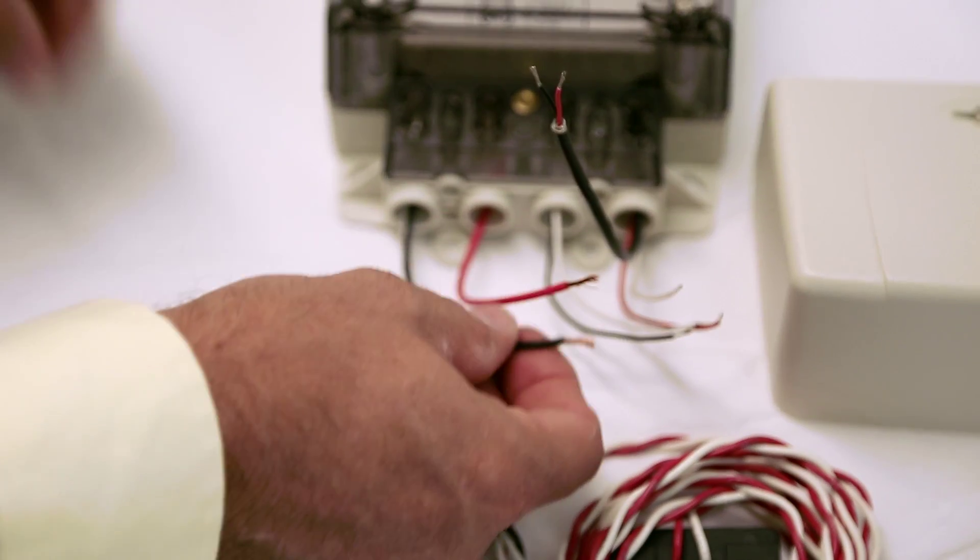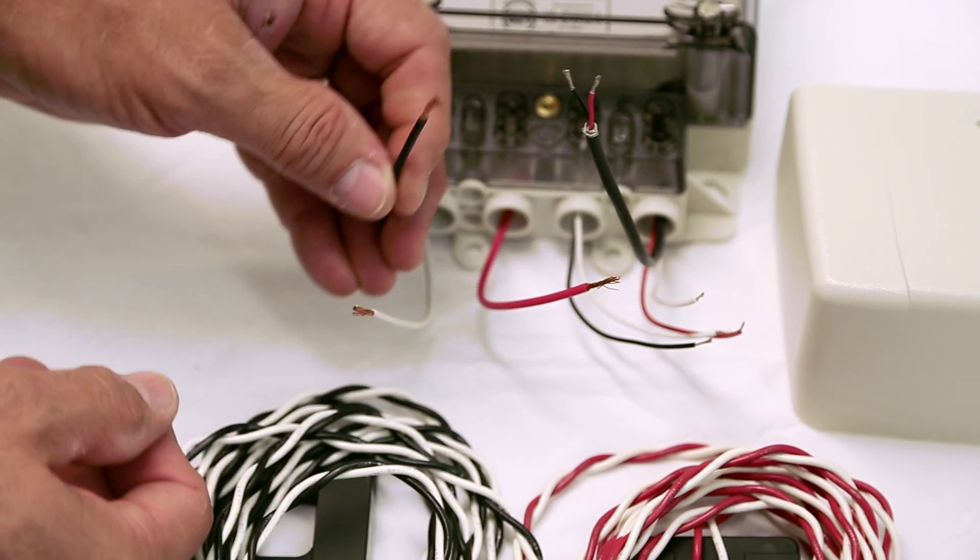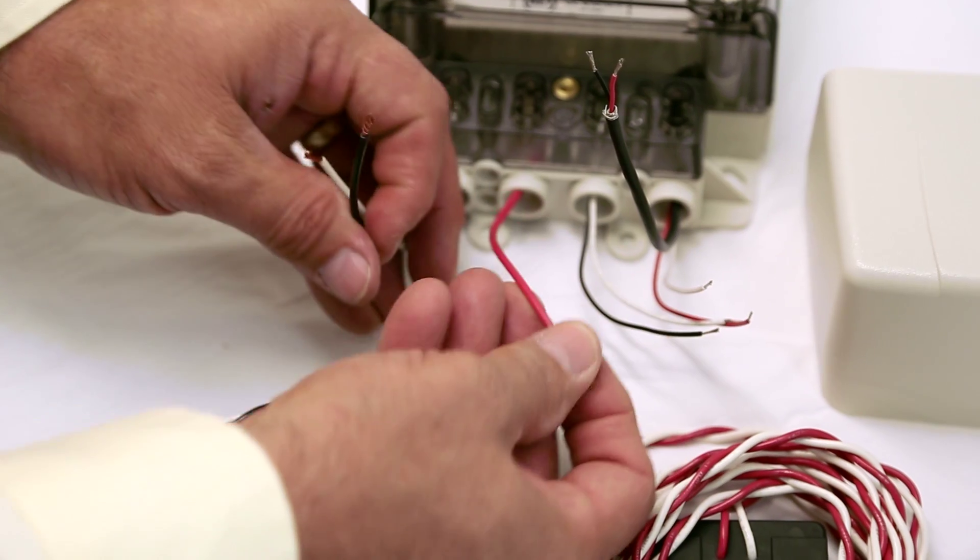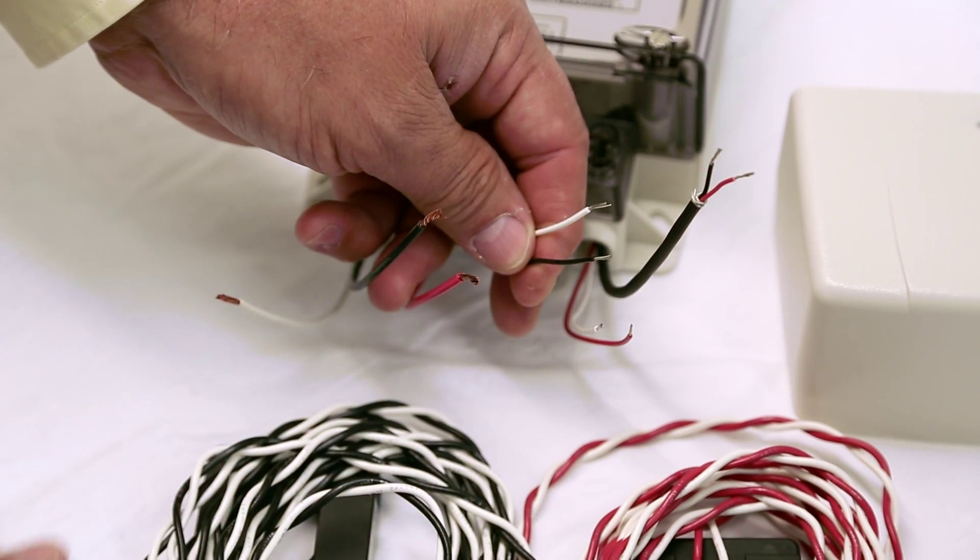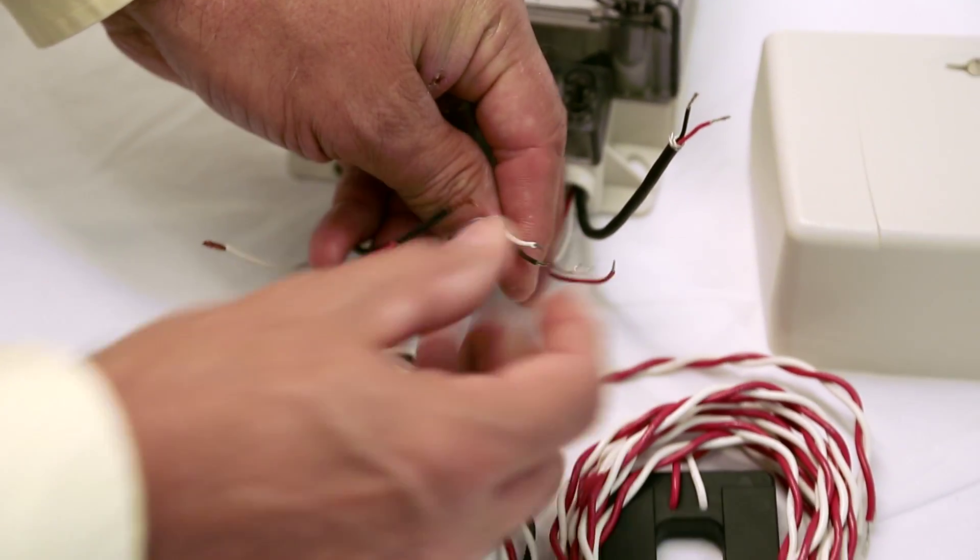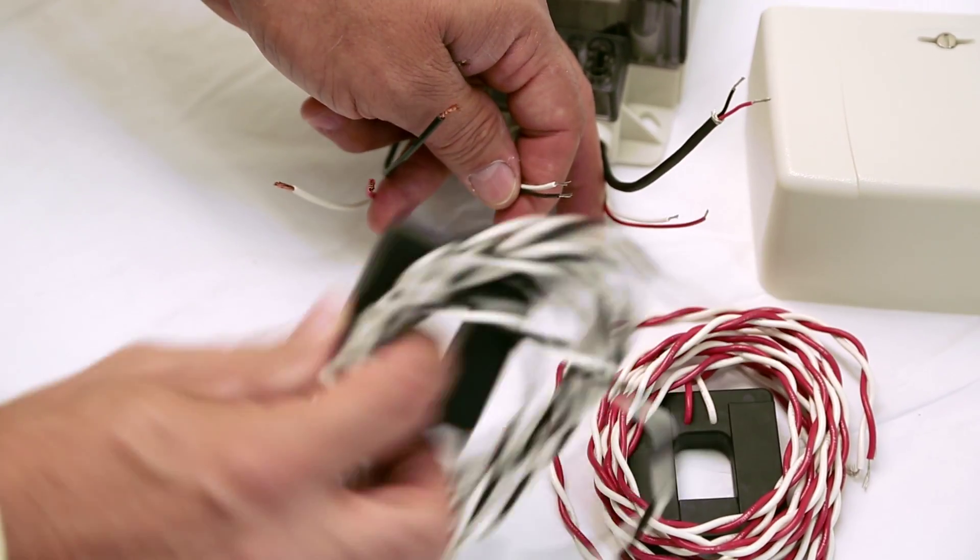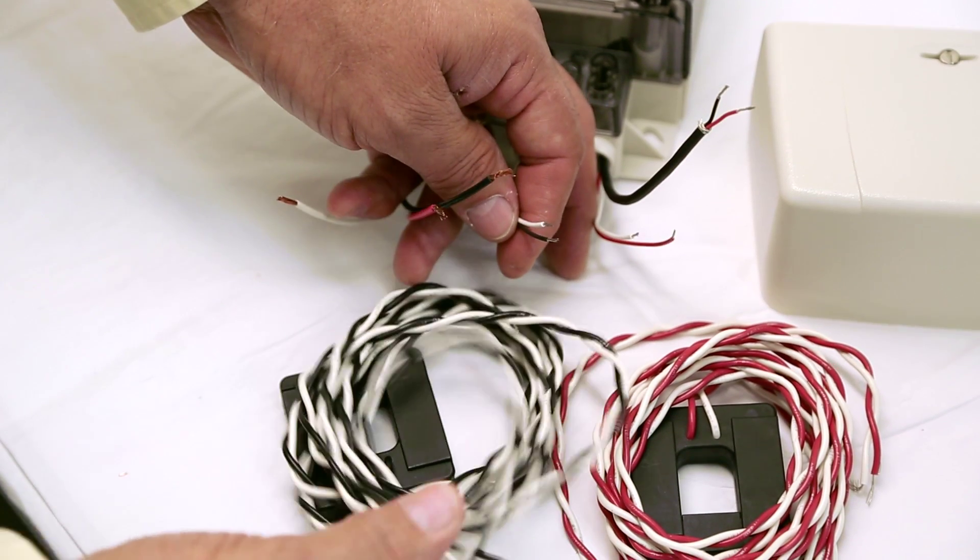These are your voltage connections: black for line one, white wire for neutral, and the red wire for line two. The black and white wires are your CT connections for the CT included with the meter that have the black and white leads.